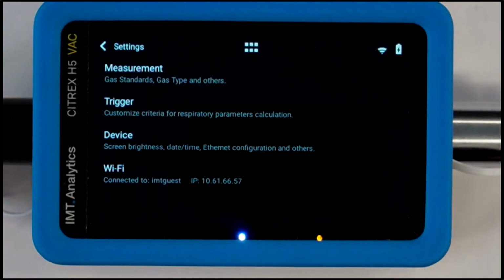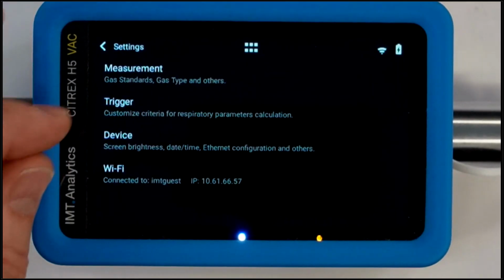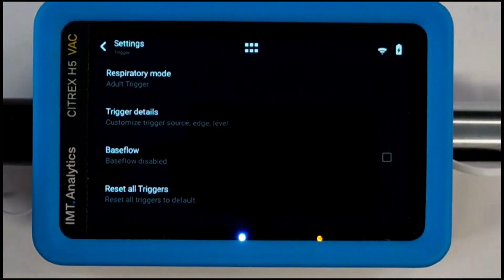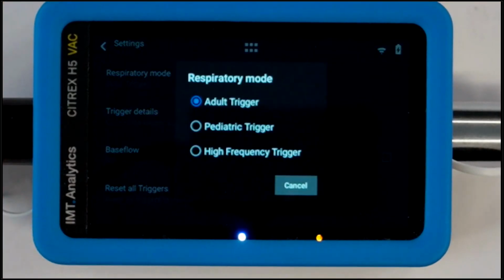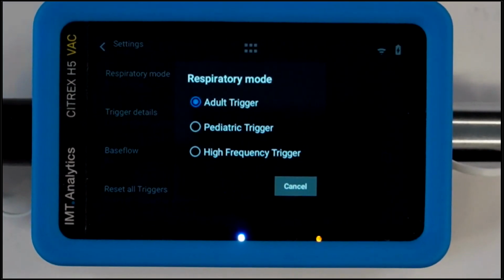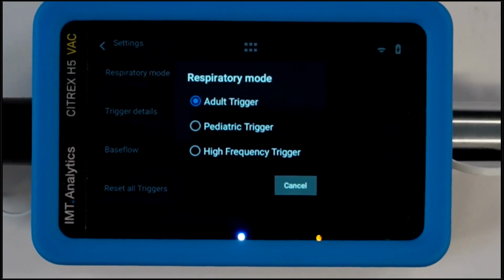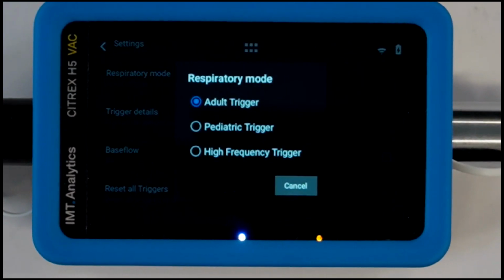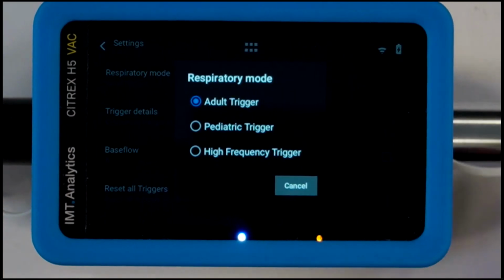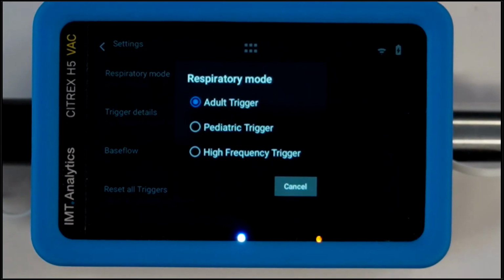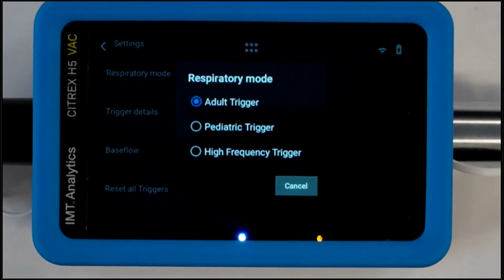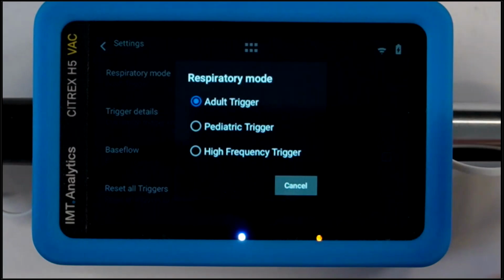Let's go back to one more thing that we want to make sure we have set correctly to prepare our device, and that's our trigger setting. So we go to triggers, respiratory mode. The H5 comes with 3 factory default trigger settings: adult, pediatric, and high frequency. So we can test pretty much any ventilator out there. You just want to make sure you're using the proper respiratory mode for the ventilator that you're testing. Today we'll be doing an adult ventilator, so we're going to leave that on adult. And by the way, each one of these is completely configurable, and you may have to use that, may not. In most cases, the defaults work fine. But if you do need to configure any of them, you can do that.